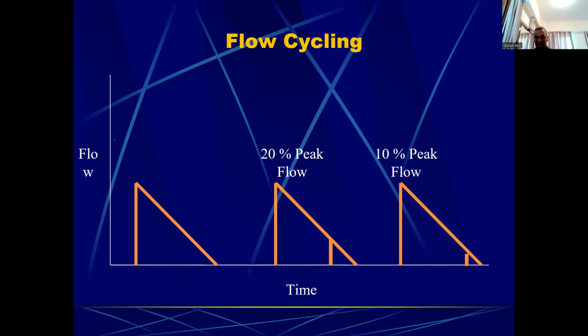Yes, so again, the sensors are inside the machine. The peak flow is reached. Patient gets what is set, for example, 20 of pressure or 200 cc of tidal volume. And the patient's inspiratory efforts are decreasing. So the flow keeps decreasing because the machine has already given the flow. Patient's effort is decreasing, so the flow is decreasing slowly because patient is not making any effort. And once the flow reaches 20%, or you can set this 20% or 10%, normally we set it at 10% or 20%. We don't change it much. And once the 10% is reached, the algorithm opens up the exhalation valve so the patient can exhale.